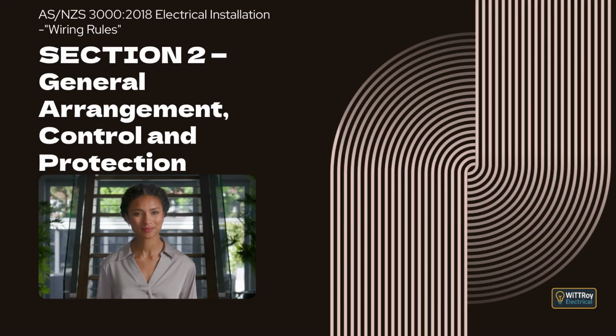Clause 2.6.3.3.2, Non-residential installations, New Zealand only. In non-residential installations, 30 mA RCD protection must be provided for socket outlets rated not more than 30 A in education and childcare facilities, including kindergartens, daycare centers, and schools up to Year 13, as well as tertiary or vocational training areas. The purpose is to protect children and young people who may not recognize shock hazards.